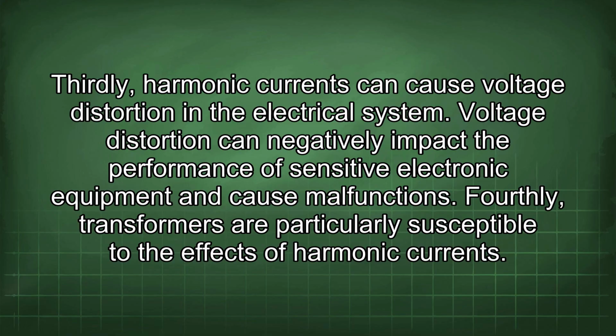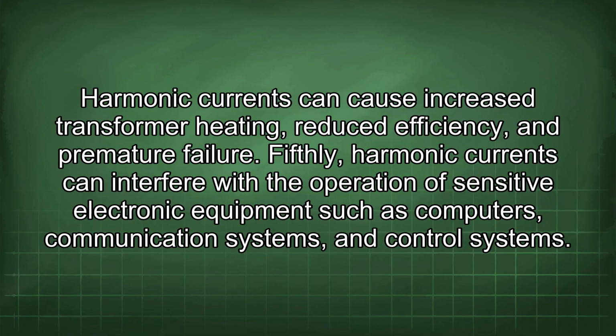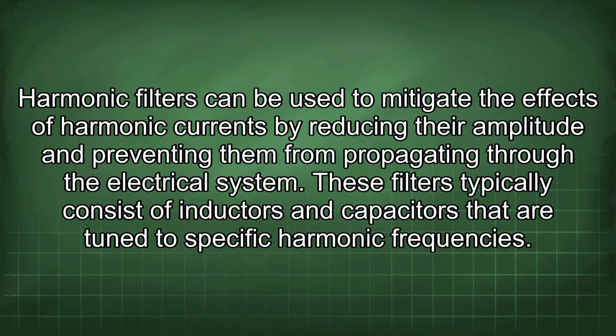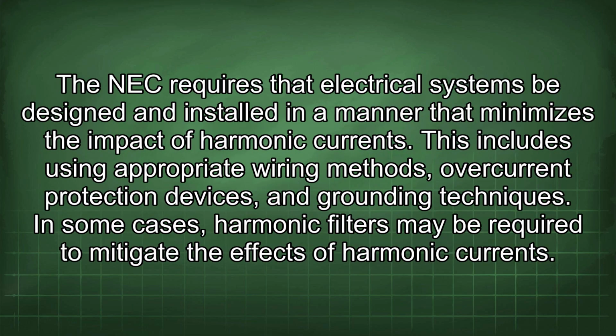Fourthly, transformers are particularly susceptible to the effects of harmonic currents. Harmonic currents can cause increased transformer heating, reduced efficiency, and premature failure. Fifthly, harmonic currents can interfere with the operation of sensitive electronic equipment such as computers, communication systems, and control systems. Harmonic filters can be used to mitigate the effects of harmonic currents by reducing their amplitude and preventing them from propagating through the electrical system. These filters typically consist of inductors and capacitors that are tuned to specific harmonic frequencies. The NEC requires that electrical systems be designed and installed in a manner that minimizes the impact of harmonic currents.